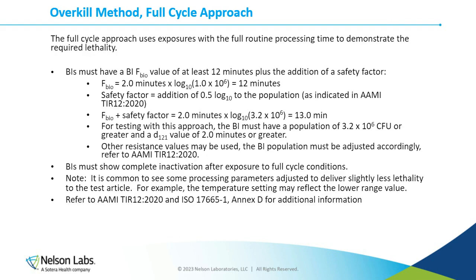The other option is the full cycle approach, although it's used much less commonly for these types of validations. For this to work, we must have BIs with very high resistance values — specifically, a BI demonstrating an Fbio value of at least 12 minutes plus a safety factor. That safety factor boils down to adding half of a log to the population required to achieve an Fbio of 12 minutes, so you're looking at a BI presenting resistance closer to 13 minutes. For both methods — half cycle or full cycle — we need to demonstrate complete BI inactivation.